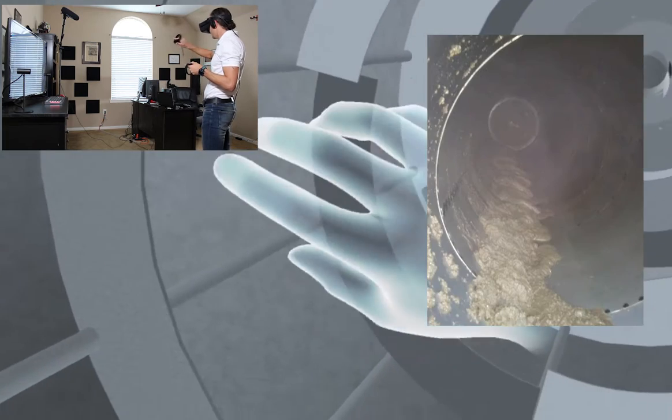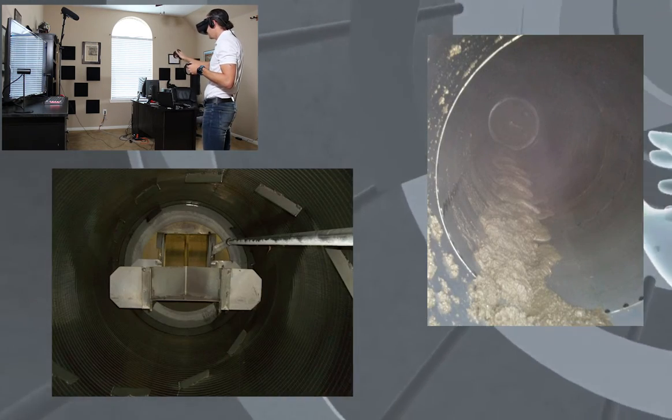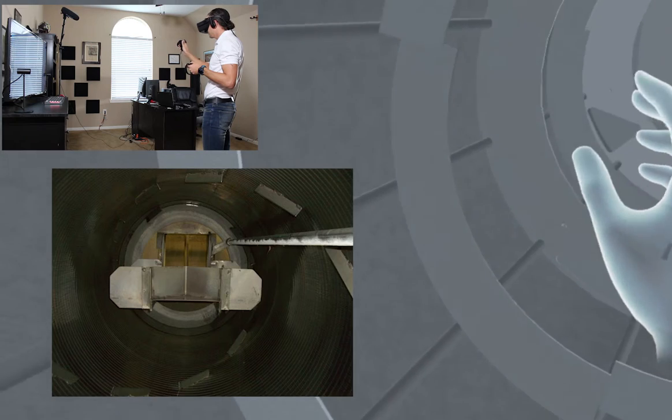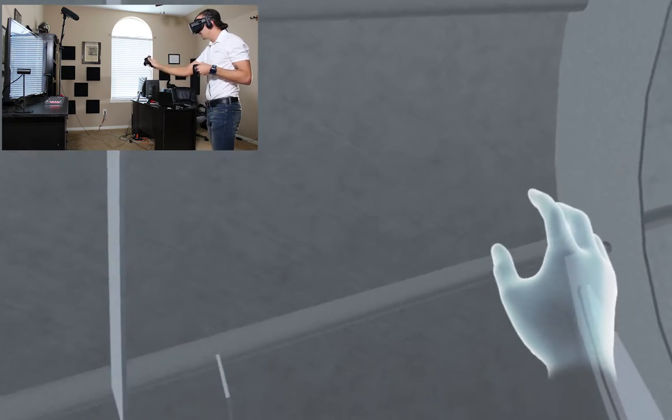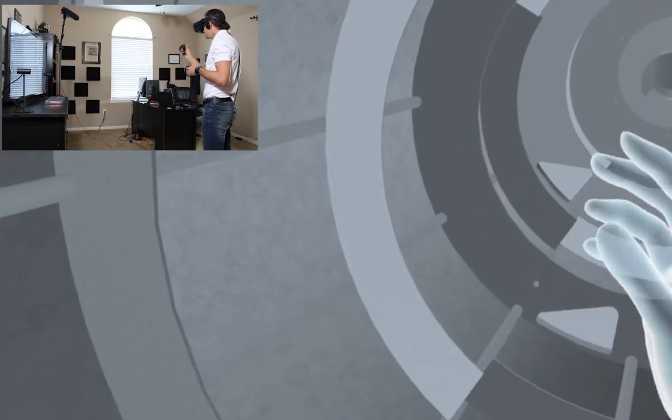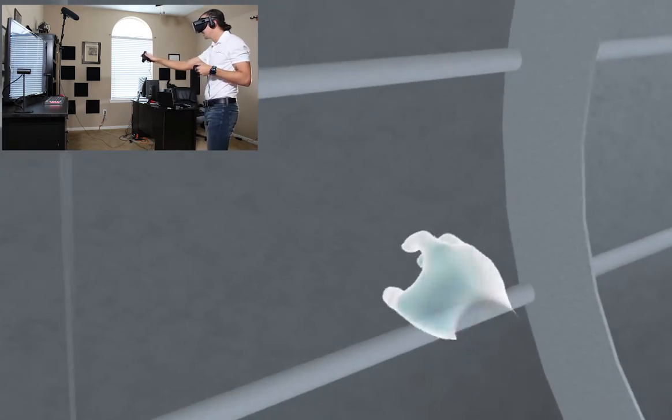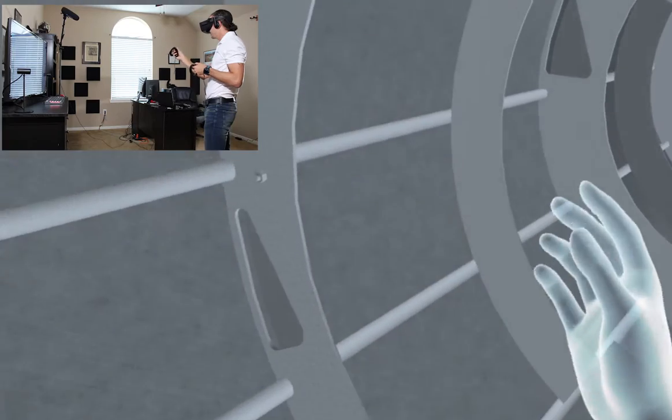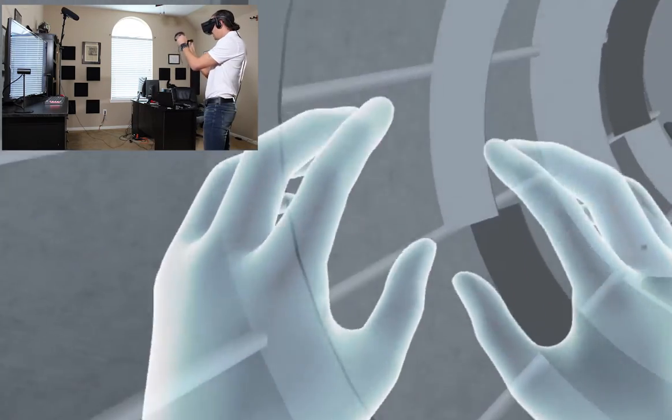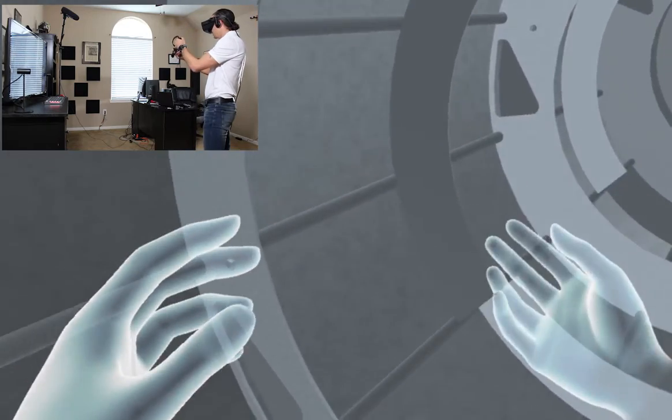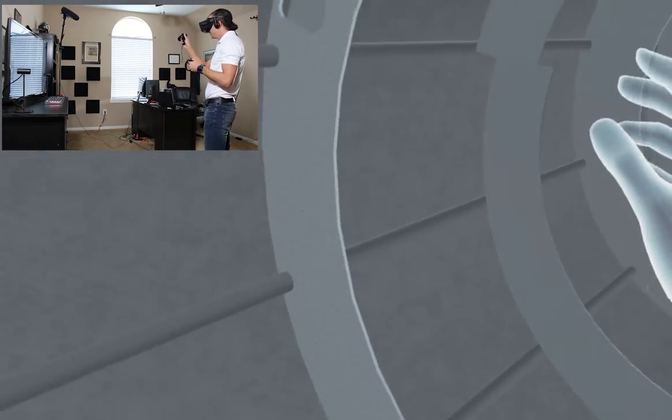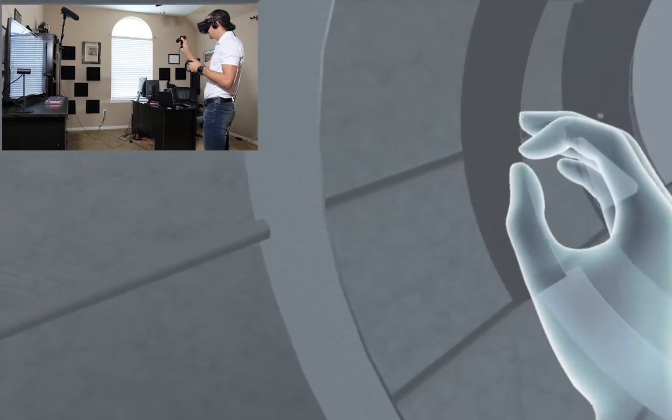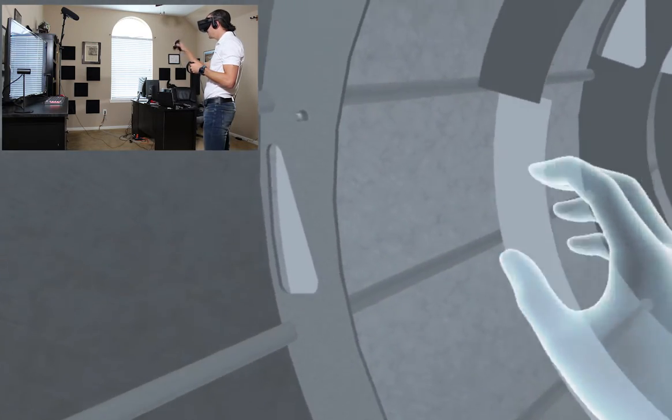Other RDTs are just empty. It's just a drum. It might have a couple of small flights, but that's it. And that's a big difference when it comes to polymer usage. So now when we've got our water and our sludge coming in contact with our screening material, now we need to look at the screening material itself. What you want here for an efficient separation is a lot of open area. Because the more area, the more place for water to go and leave the system. However, you have to have the opening sizes, the individual opening sizes, as small as possible.